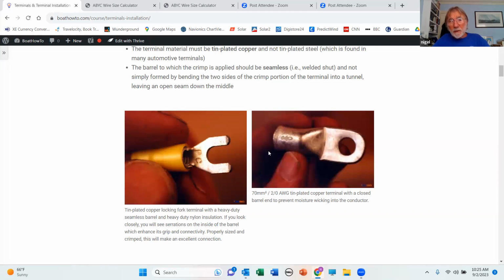And then for the larger terminals, this is a 2-aught terminal. You can see here it says 2-aught. Ideally, we want a closed end to the terminal like this so it stops moisture wicking up into it. And then we need to crimp it.